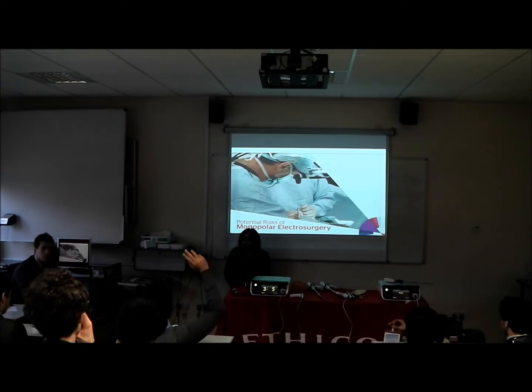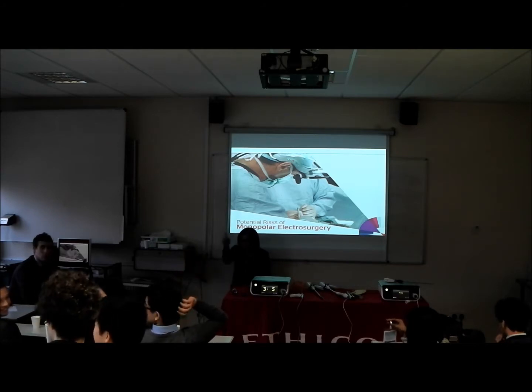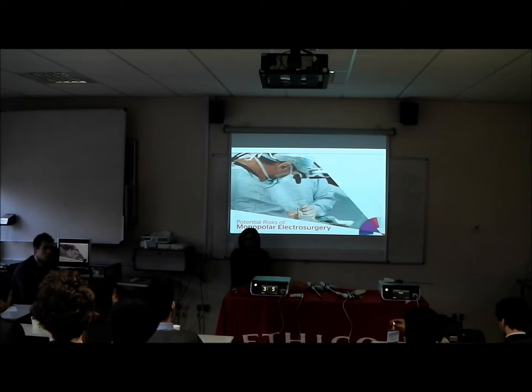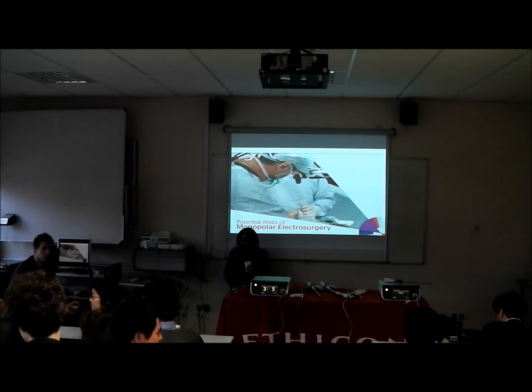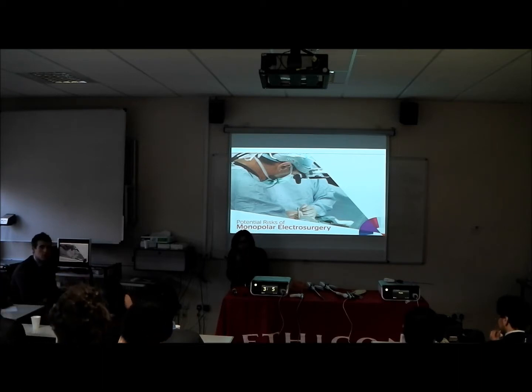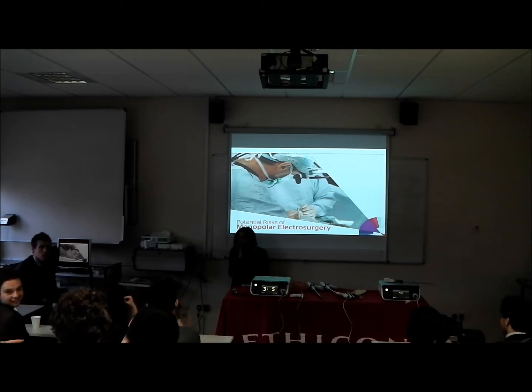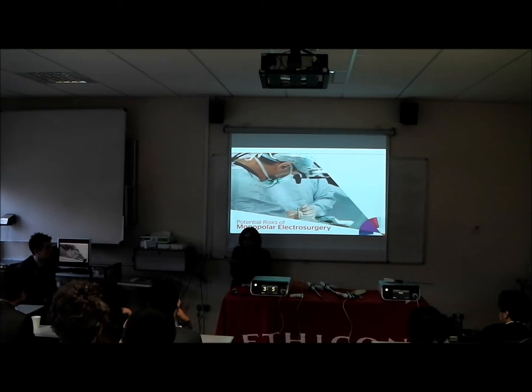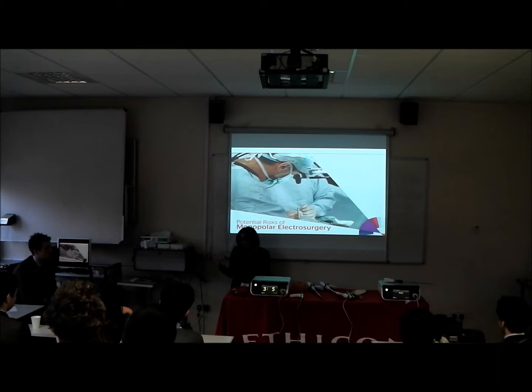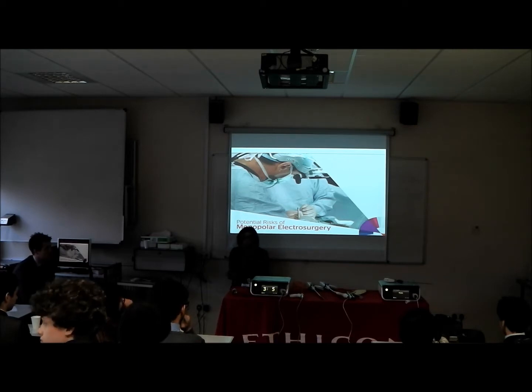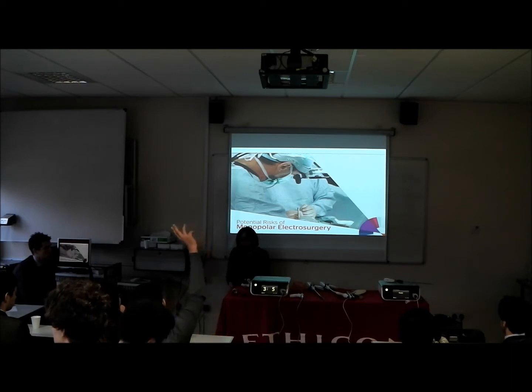What else can go wrong? Spray damage as well. Yeah, that's it, spray damage. That's the most basic. What if it's a critical moment, and you have to cut that tissue at that moment, and then the system breaks down? Yes, that can happen. If you were about to cut and the diathermy machine stops working, that's fine. Either you use an alternative energy device, which I'm going to explain to you, the harmonic and other things that we have, or we just don't use any of these devices. We just open the patient up and stitch it, because you will always have sutures available.